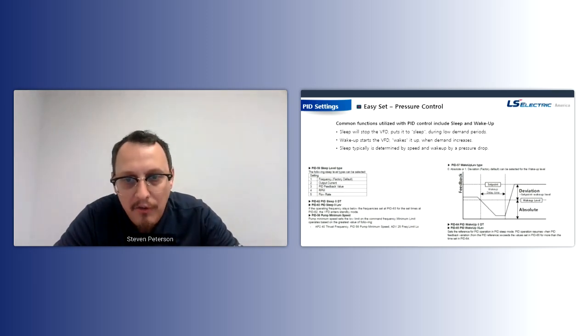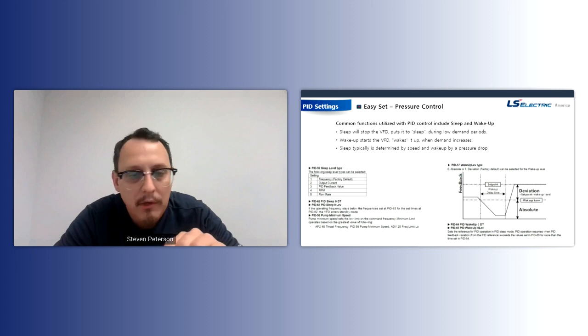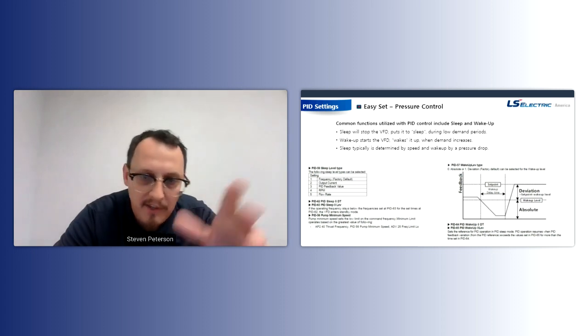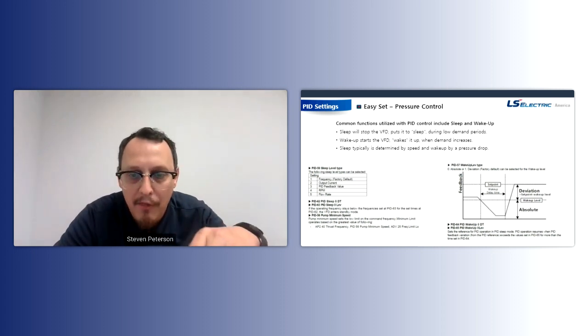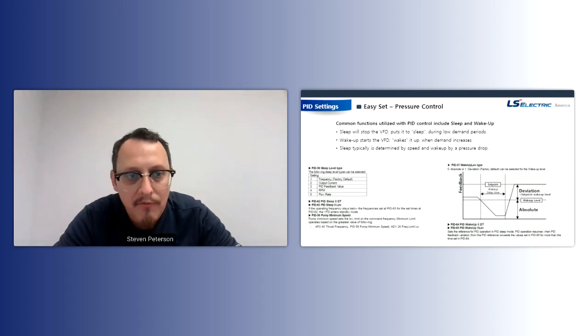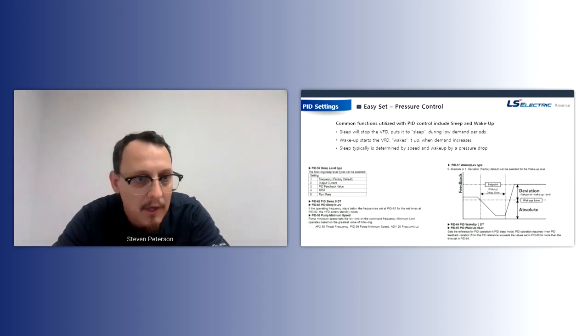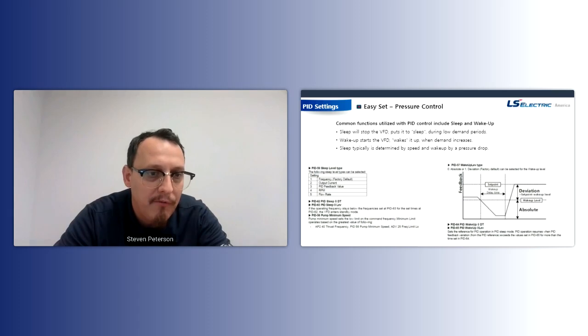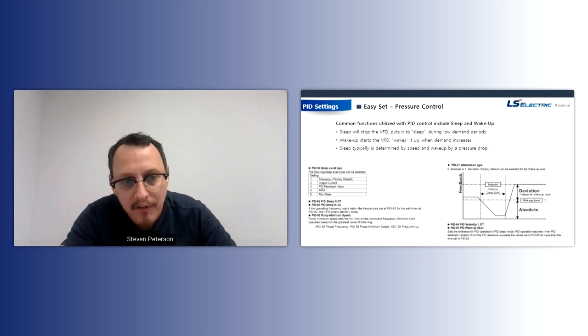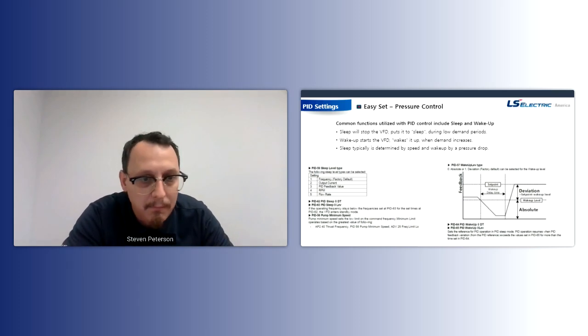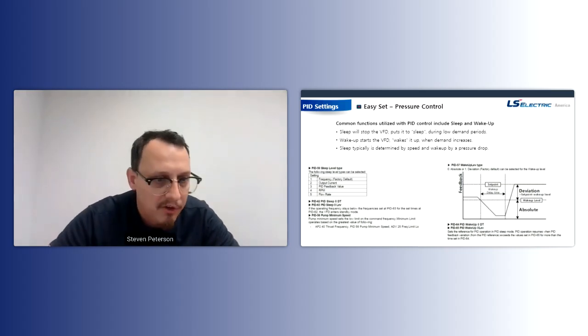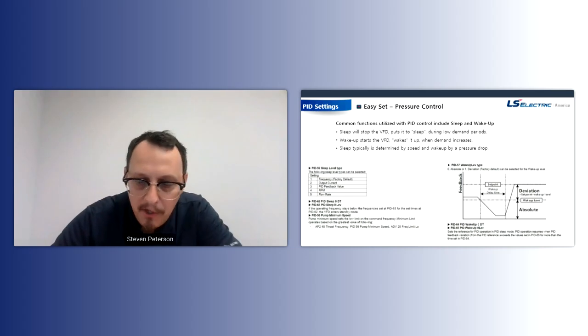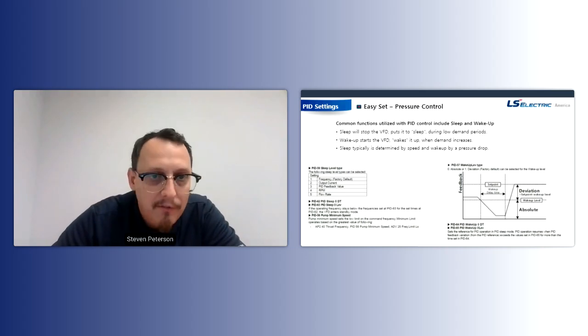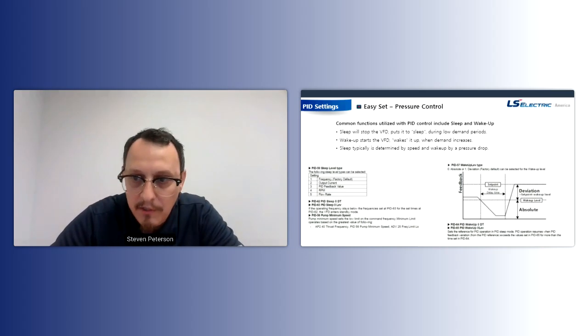I kind of like deviation because deviation follows your set point. So if you change your set point from 60 to 70 psi, it'll follow that with a 10 psi deviation. If you want, you could change it to absolute. You could also customize your sleep level. You can make it based on output current, on PID feedback value, on speed as an RPM, or on flow rate. Okay, so it's all customizable. The H100 Plus has the most options for all of this PID stuff out of all of our VFDs.